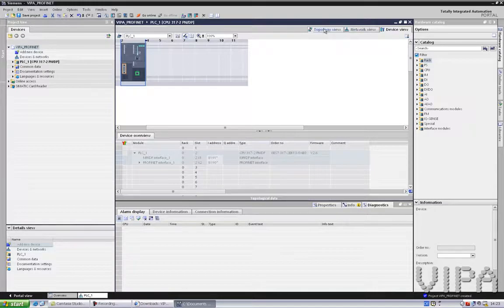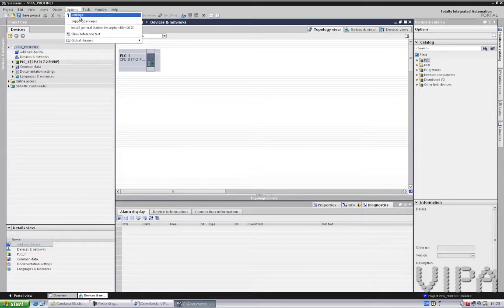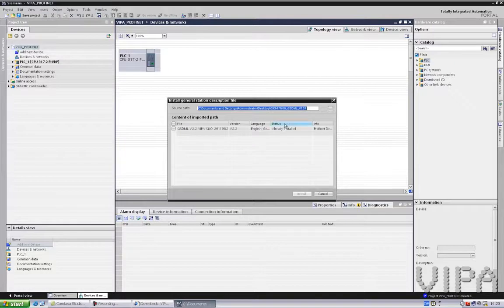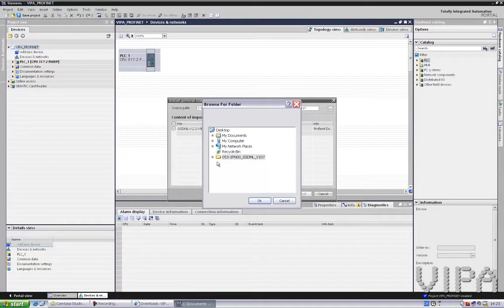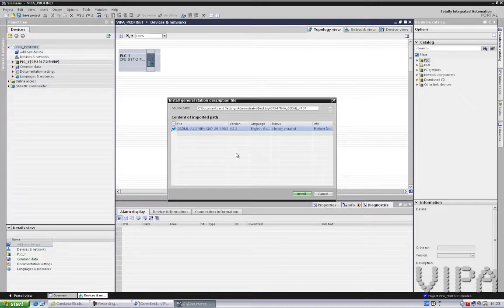Let's go to the topology view. The first thing to do is install the GSD file. You can do this over here — Install General Station Description file. You go to the folder on your desktop where you have downloaded and unzipped it, and then you can install it. Now I have done this already. I just want to tell you that if you do this, TIA Portal will have to close and restart. And then you can continue your configuration.